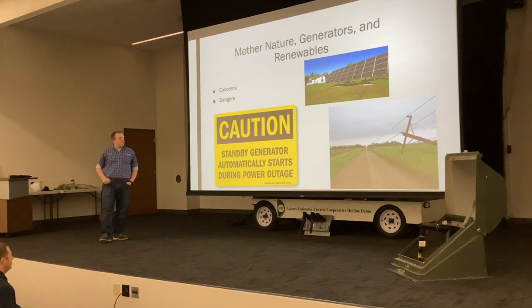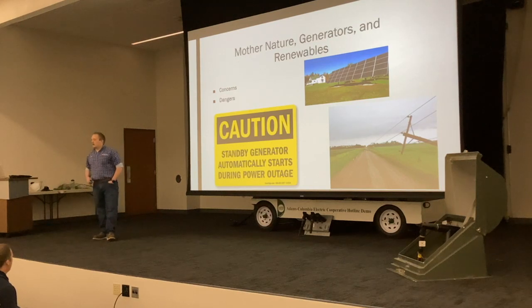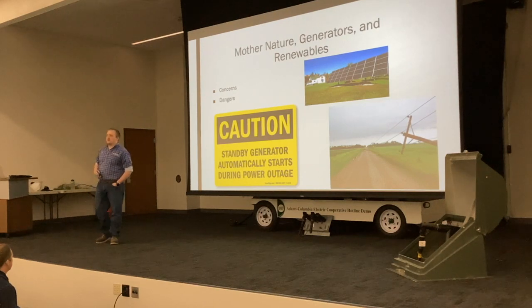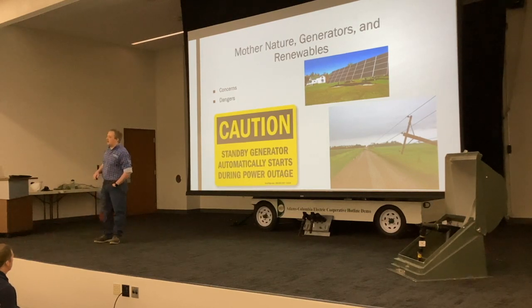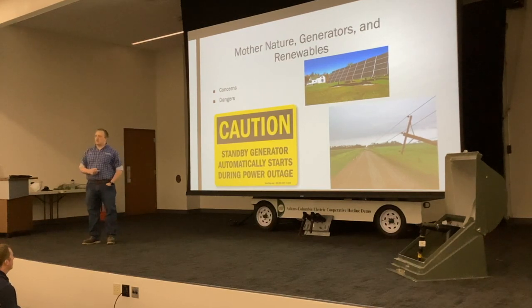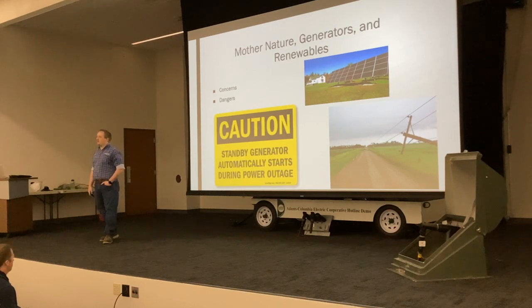So we've got Mother Nature, generators, and renewables. I talked about how we're going to backfeed our hotline demo. I just want to make you aware that even when our devices work properly and the lines come off, if somebody is impatient and decides to fire up a generator and try to backfeed their whole house, and they do not have the proper disconnects or take any precautions, they can backfeed with a generator through their meter, through the secondary line, into the transformer. And what did we say would happen if you put 120, 240 into a transformer? The other side's going to come out 7200, right? So that is an example of backfeed.